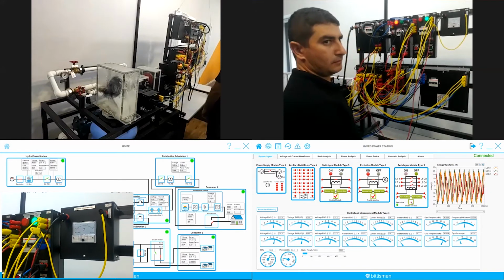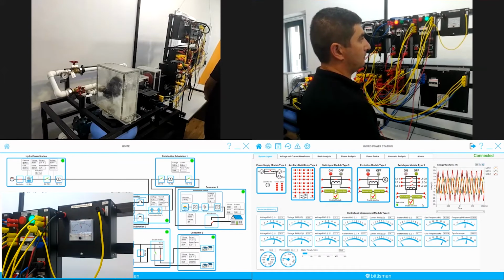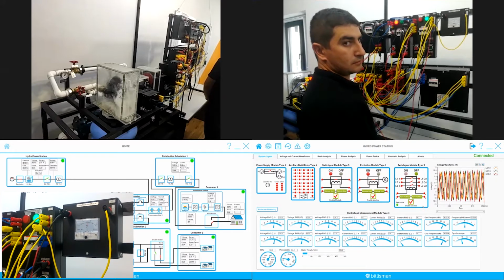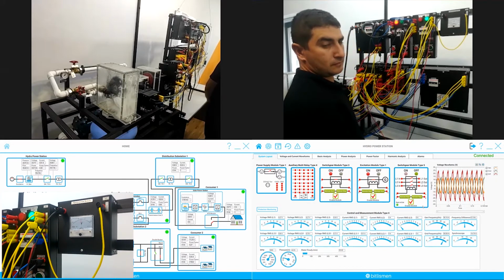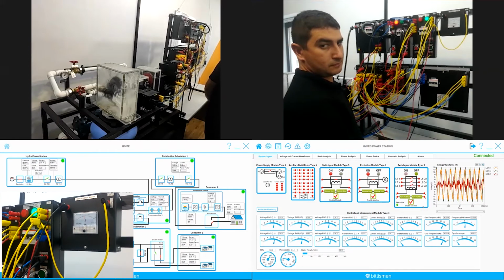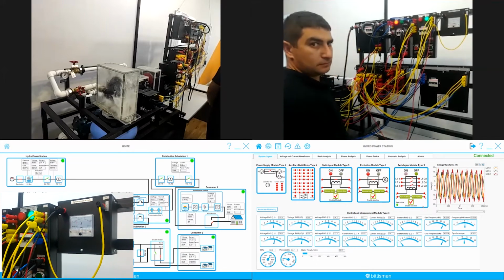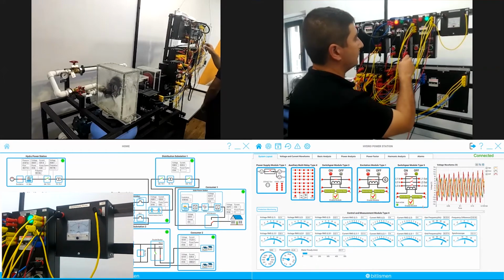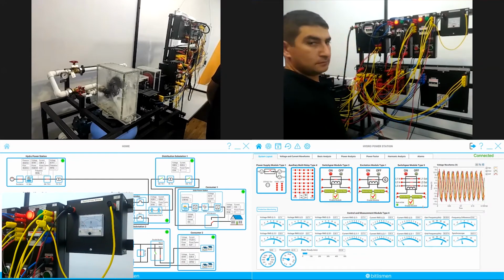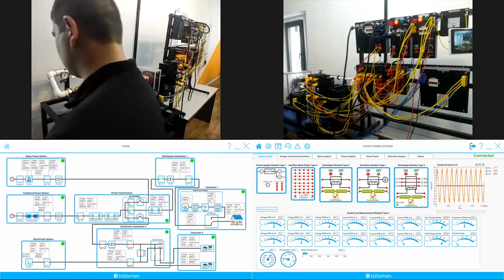And here we should enable the switchgear module type 5, which is responsible for connecting the hydropower station to the microgrid. And using the synchroscope module, we should connect the hydropower station to the grid at the time when the arrow reaches zero. Now the hydropower station is connected to the grid.